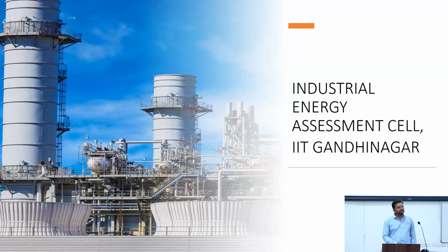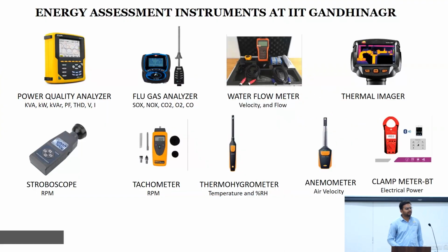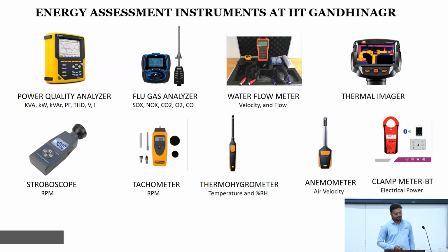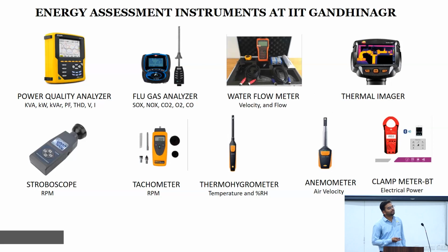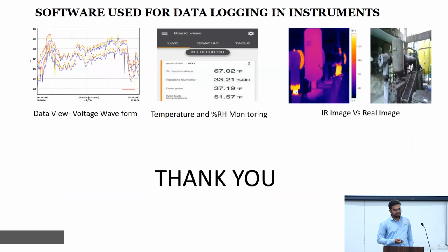The major instruments that we are using during the energy assessment activity are the thermal imager, the flue gas analyzer, water flow meter, power quality analyzer, stroboscope, and the tachometer. For specific measurement of RH and temperature, we have Bluetooth operated thermography, Bluetooth operated temperature hygrometer, and anemometers, and we also have some clip-on meters for the energy measurements.